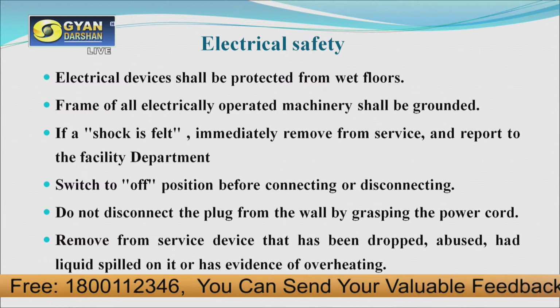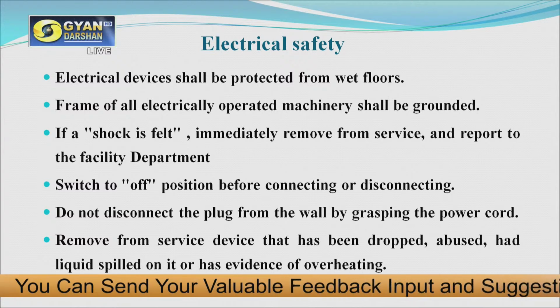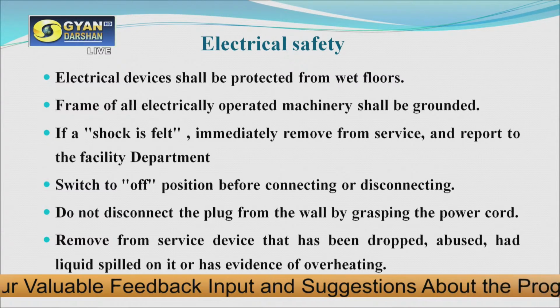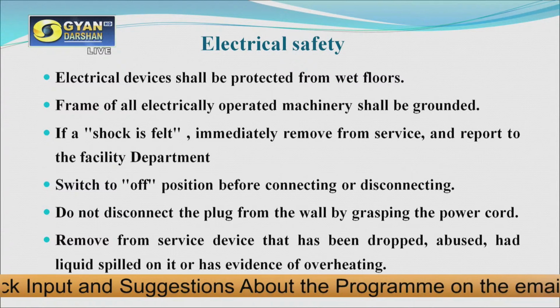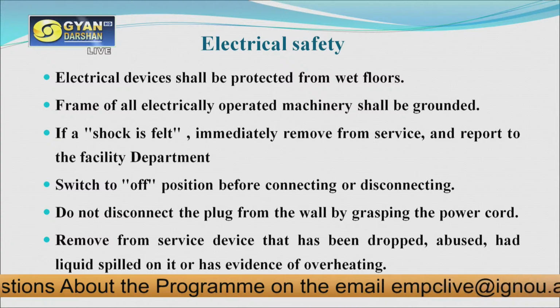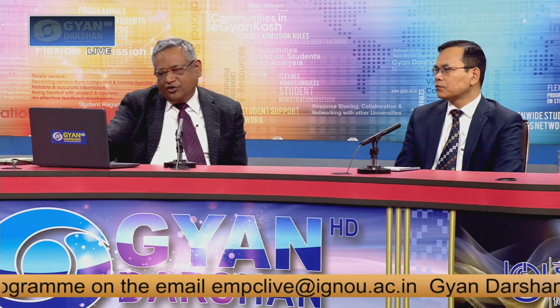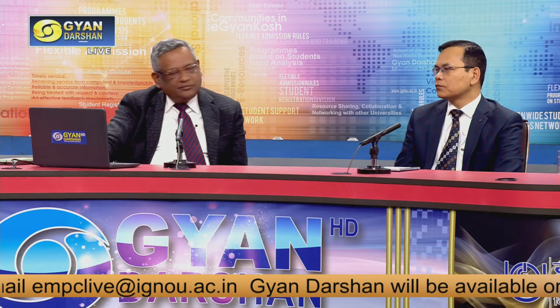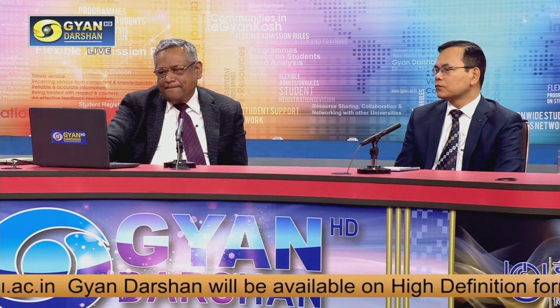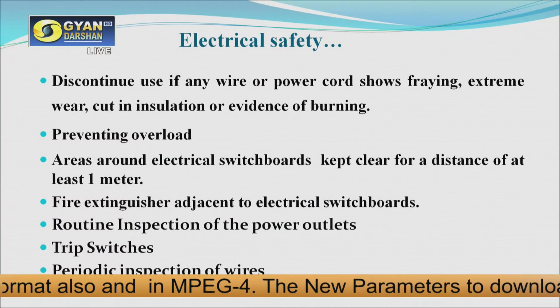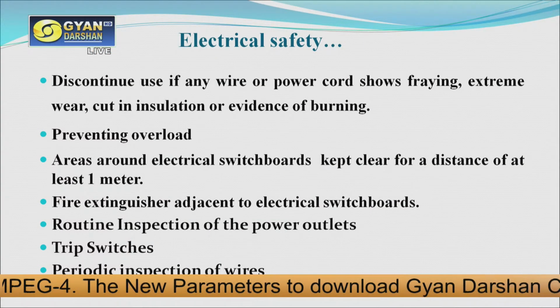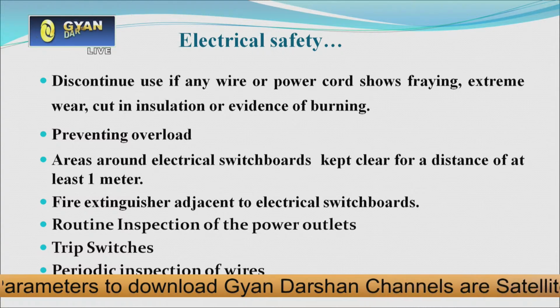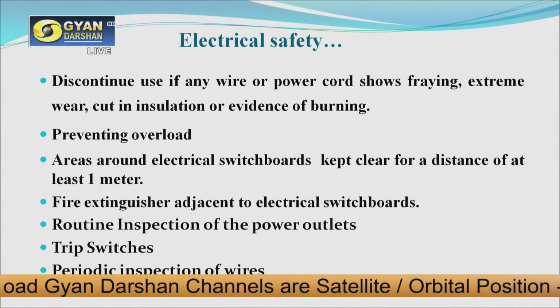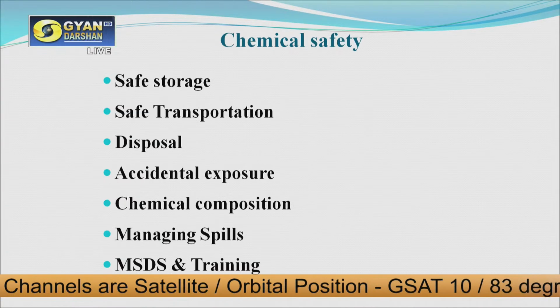So we have the practice of switching off and switching on, because most things are manual in a hospital unless it is an automated system. You can have automation with a control panel for electrical, air conditioning, fire, but pretty much it is manual because automated systems are a little expensive. We can have trip switches, because when there is an overload you can trip off and then trip on. Similarly, the generator and the LT panel have to be connected by a bus bar and bus coupler at the AMF panel, so that nobody comes and manually changes it.